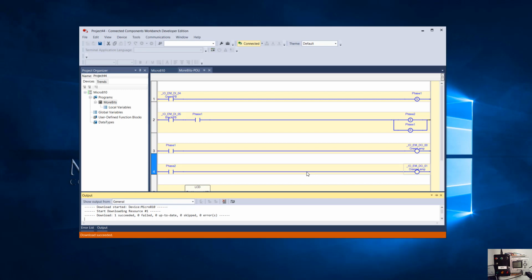Okay, so you can see all our rungs are false at the moment. So I'm going to hit the green push button, and you can see on the PLC trainer the green lamp came on, and you can see that everywhere that phase 1 bit, my status bit, is referenced, the instruction is orange, because as soon as I hit that green push button, it set phase 1 to be true. So that phase 1 bit is sealed in now. It's not going to go to a 0 until I do the reset here. So to reset it, I hit the black push button, and now the orange lamp is energized and I'm in phase 2. And if you look, the phase 1 bit is now 0 or false because we reset it here.